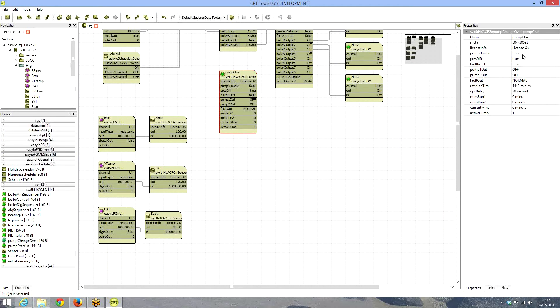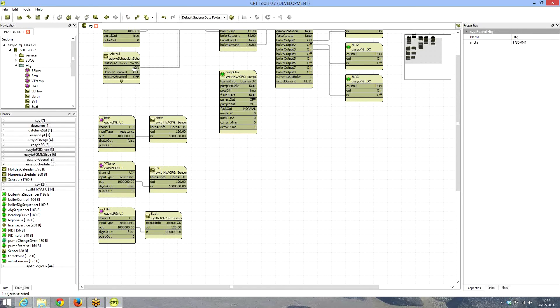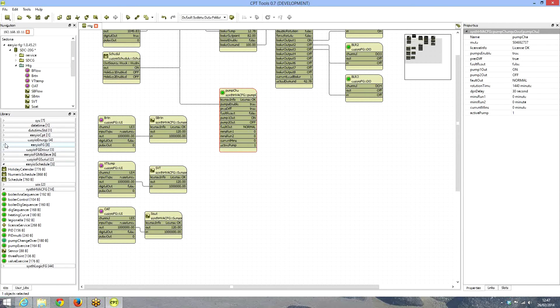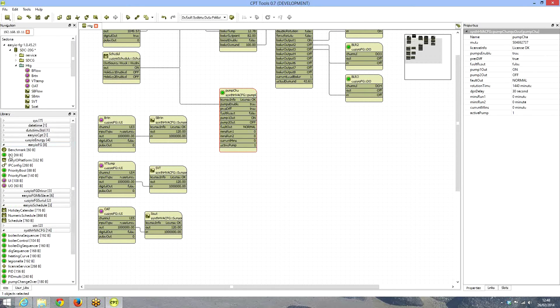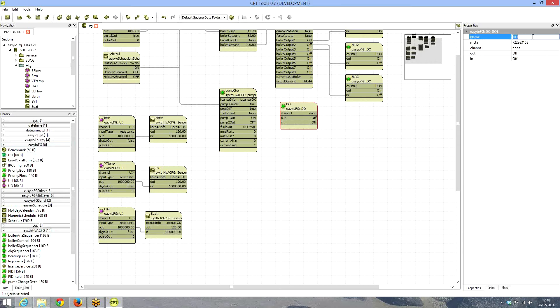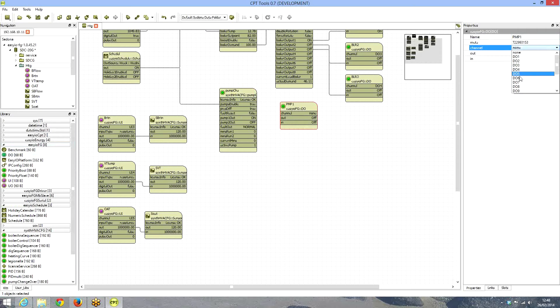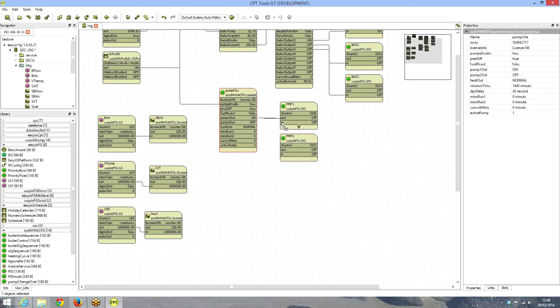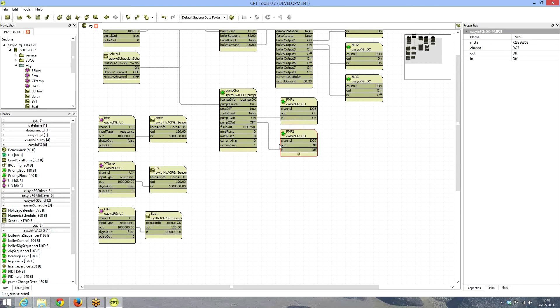We bring in the pump changeover object. On that object we have a 'pumps enable' input and a pressure differential input. We enable the pumps from the same schedule. From the IO area on the left, we bring digital output 6 for pump 1 and digital output 7 for pump 2, then link pump 1 output and pump 2 output accordingly. We now have a pump rotation object in place.